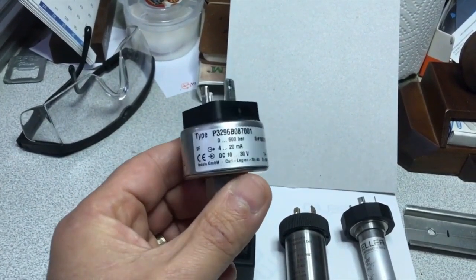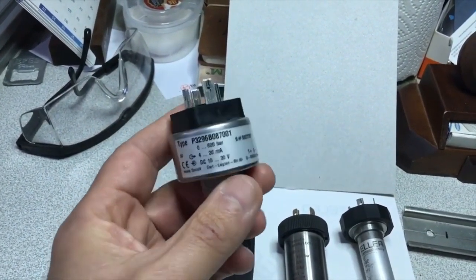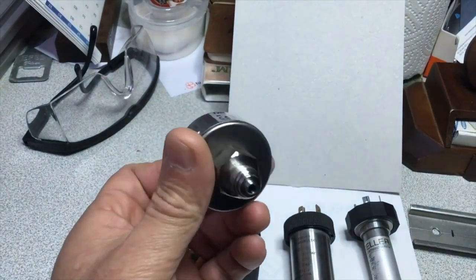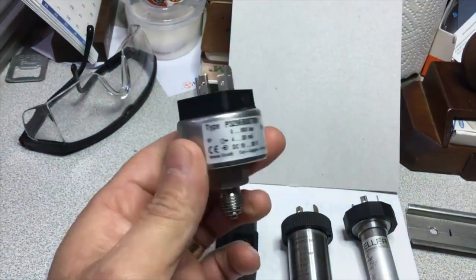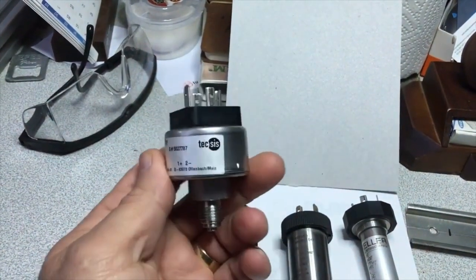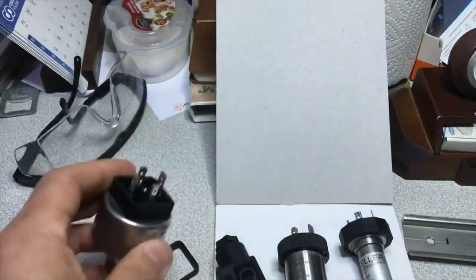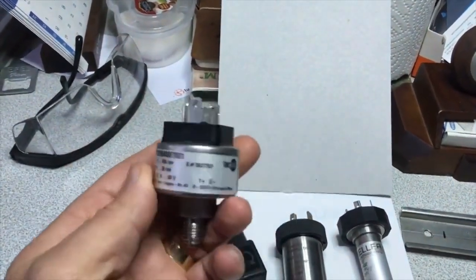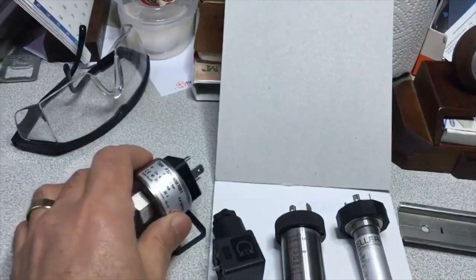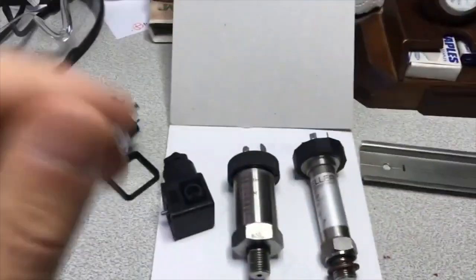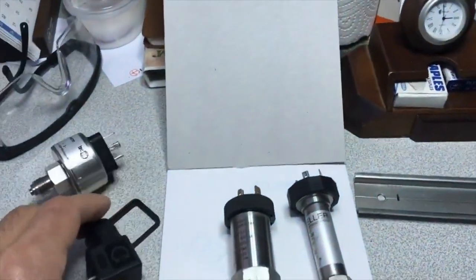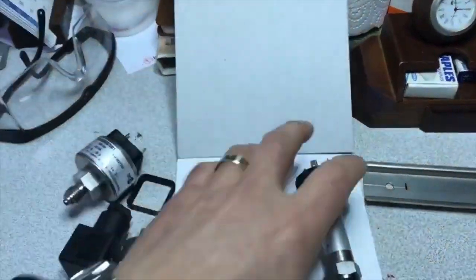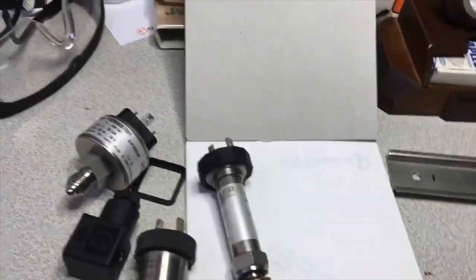In the case of 4 to 20 milliamperes, when the cable is broken or the sensor is broken and we can't get an output, the controller will detect it and this will generate an error code, not 0 bars. In this case, it will be possible to find and fix the error in the system, so that we can prevent some accidents. That's why sensors with 4 to 20 milliamps output would be a better choice in such applications, I personally think. Let's examine how the connection will be now.